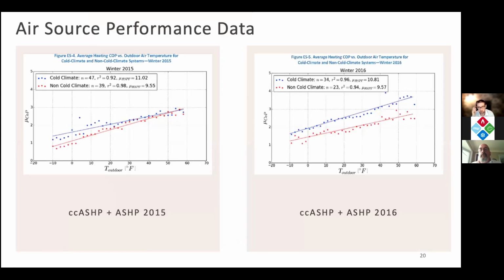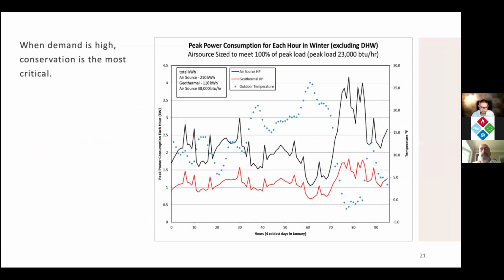Air source heat pumps are a great option and will play a major role in decarbonizing space conditioning and water heating. But it's important to note that the days you need the energy most and need the most efficiency are the days air source heat pumps are least efficient. So peak heating and peak cooling is when these systems don't perform as well as they could. Performance has been increasing over the years with improving compressor technologies and cold climate air source heat pumps. As you can see in these charts, when we get to -10, we're still at a COP above 1, around 1.5. That has a major impact at scale on the grid.